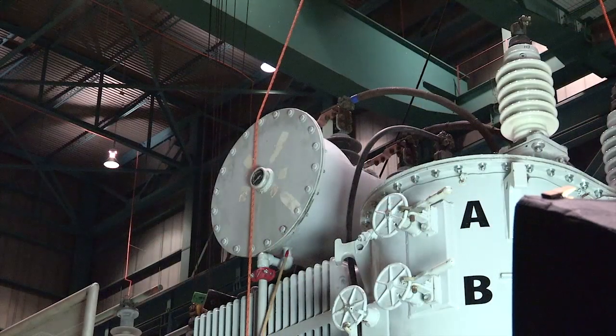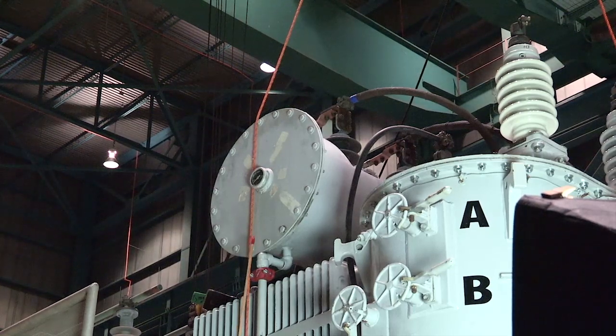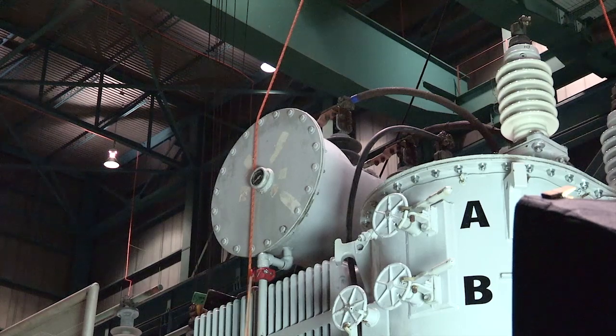Next, we're going to be looking at the conservator. We want to inspect and make sure all the bolts are tight. You want to look at the mounting bolts holding the conservator to the tank. We want to look at the sight gauge, make sure there's no leaks, make sure everything's tight. You want to inspect the piping, make sure everything's tight, no leaks, no damage.